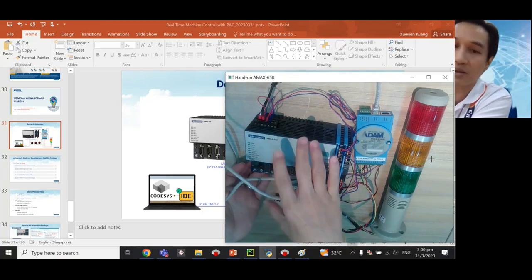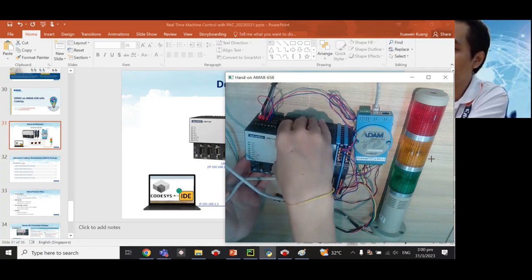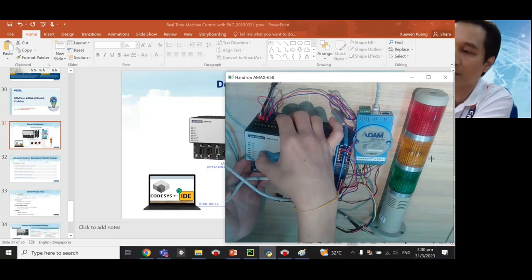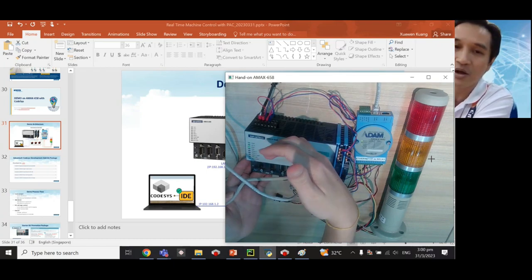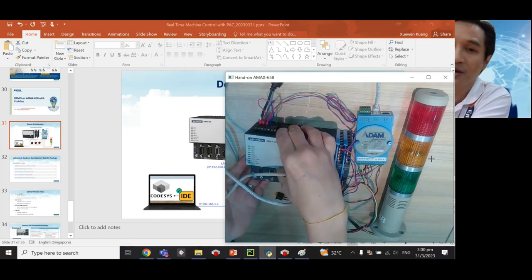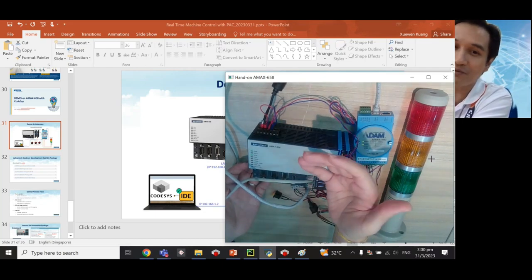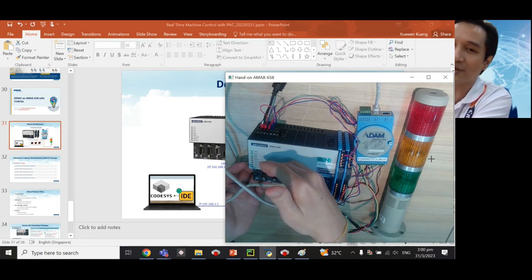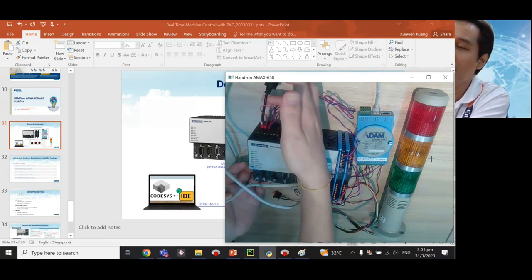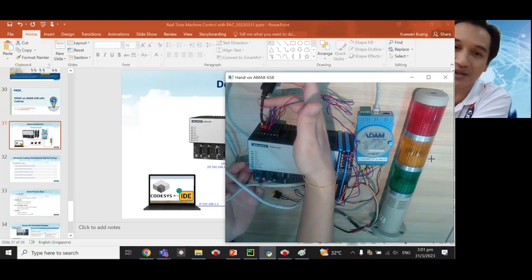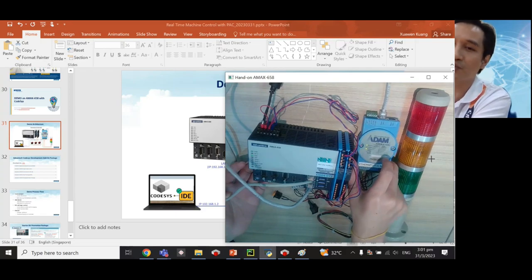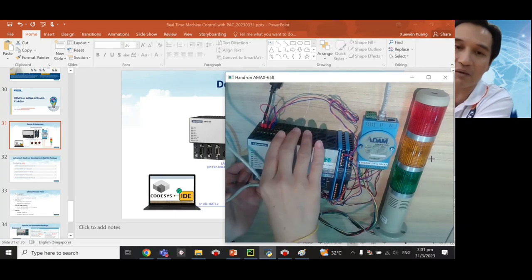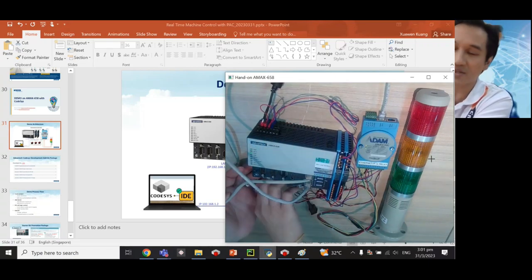Sometimes, if the internal CPU is overheating, this LED will be triggered. They write down "over temperature". We also have another error LED, for voltage. What does the error voltage mean? The first time I tested this hardware, the power supply I was using was 19 volt. I didn't check the data sheet and just connected the power. This error LED came on. After that, I found out the issue was that I was not using 24 volt power. You have to use 24 volt power. You cannot use it like our normal ADAM, which takes up to 30 volt. It's not like that. This hardware is designed for a 24 volt DC power supply. You need it.